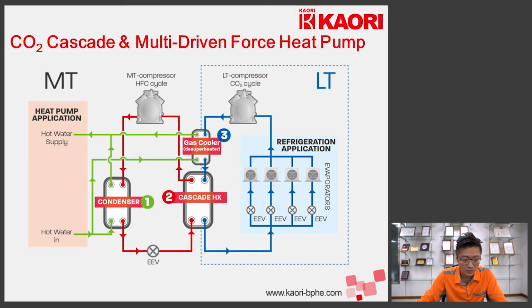Here we have a CO2 cascade and multi-driven force heat pump. There are 3 main components which require brazed plate heat exchangers: the condenser, the cascade heat exchanger, and the gas cooler. Instead of having 3 separate brazed plate heat exchangers, we can just use one single multiple circuit unit, making the system a whole lot simpler, lighter, and cheaper.